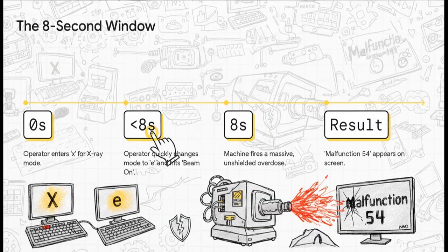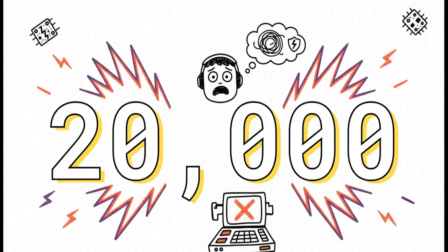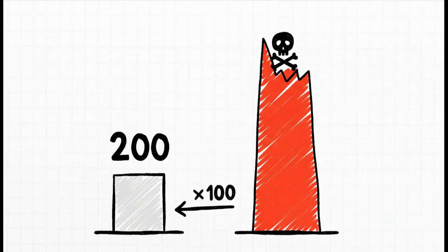The screen confirmed electron mode, everything looked good, so she hit beam on. The machine fired, and then a cryptic message appeared. Malfunction 54. What that operator had no way of knowing was that in that split second, the machine had just delivered an estimated dose of, get this, 20,000 rads. And to put that number into perspective for you, the intended therapeutic dose was only 200 rads. This patient received 100 times that amount. It was a fatal dose.